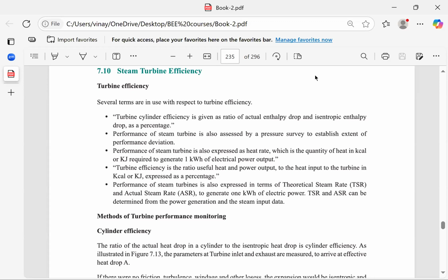So what should have been the loss? If the actual loss is more, take the ratio of actual loss upon ideal loss, and that gives you the turbine stage efficiency. This definition, the ratio of actual enthalpy drop versus isentropic enthalpy drop, expressed as a percentage, is the turbine cylinder efficiency.